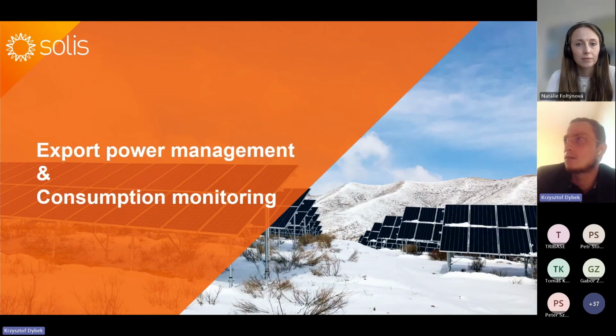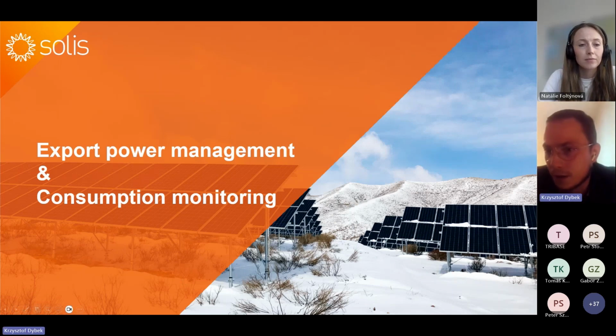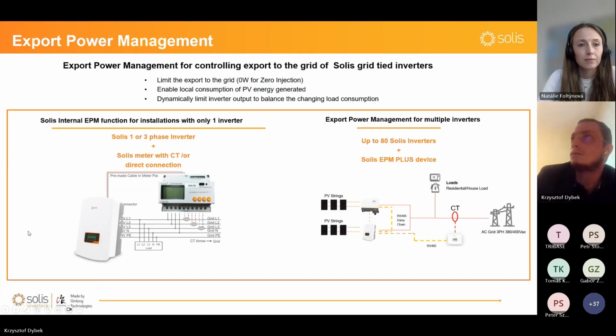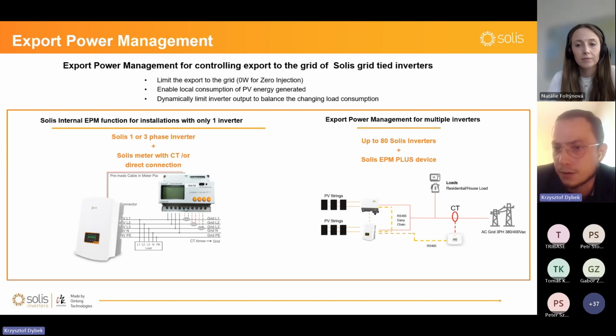Yeah, and about this EPM device, because this is crucial for commercial scale plants. As we all know, we cannot feed the grid without any penalty. So in short, we have an external device to hang on the wall, called Export Power Manager. It controls energy flow through the system and allows or doesn't allow export energy. And this is extremely important, as there is no joke with grid operators at this point. Injection of energy to the grid makes the grid unstable and leads to damaged devices connected at houses.